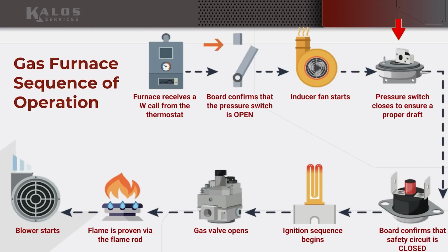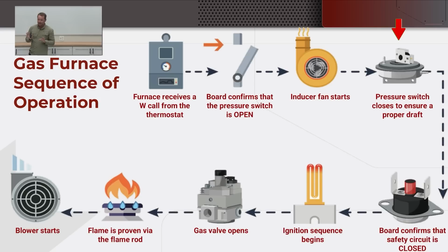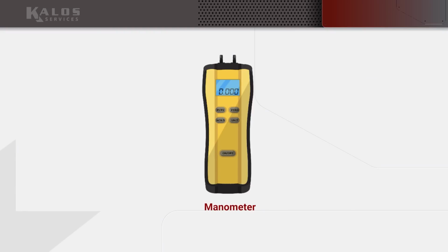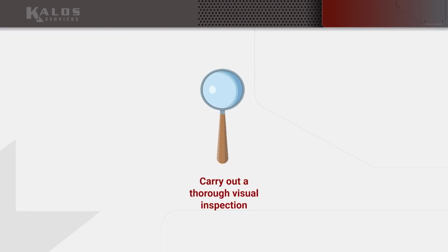And it's a negative pressure switch for the stuff we work on. So it's looking for this negative pressure. If it doesn't close, because this is going to happen a lot when you work on gas appliances, that switch doesn't close, it's not a bad switch. Sometimes it's a bad switch, but it's almost never a bad switch. Why isn't it closing? Because there's not the pressure that it's looking for, right? How could you confirm? Well, you could use a manometer, but generally you're going to start doing a visual inspection.